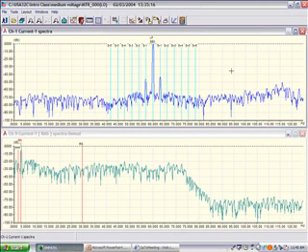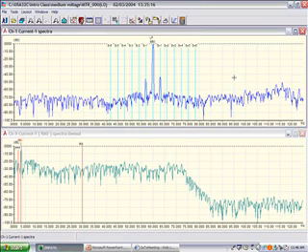The interesting story behind this is vibration analysis was used. They thought they saw broken rotor bars. They took this compressor motor out. This compressor motor is a 500 horsepower, 1765, 4160 volt, 120 amp machine down here in my CT and PT ratios. Okay. Sent it into the repair shop. The repair shop replaced the bearings, put a nice paint job on the motor and sent it back. So, there was no problem.